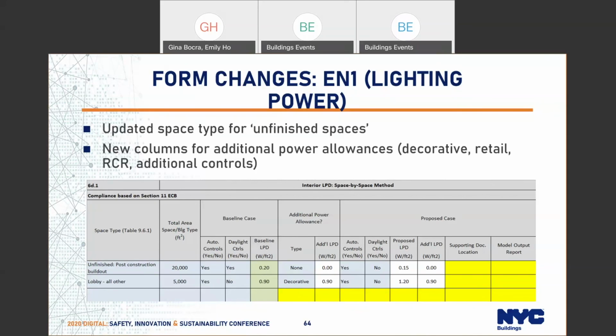So on the lighting tab, we added one of the new space types we have in the code. I don't know if we mentioned that earlier, but if you have a core and shell building, the unfinished space in that building for the post-construction build-out is now assigned a baseline value of 0.2. There's a lot of confusion on what that LPD should be, and a lot of savings was trying to be taken if it was supposed to be an office space, but the lighting wasn't yet designed. So now we have a baseline value of 0.2 for those unfinished spaces.